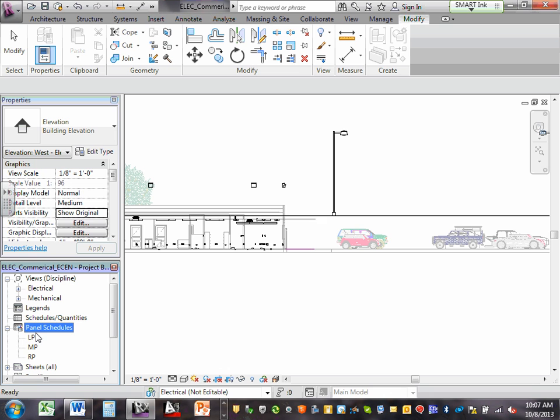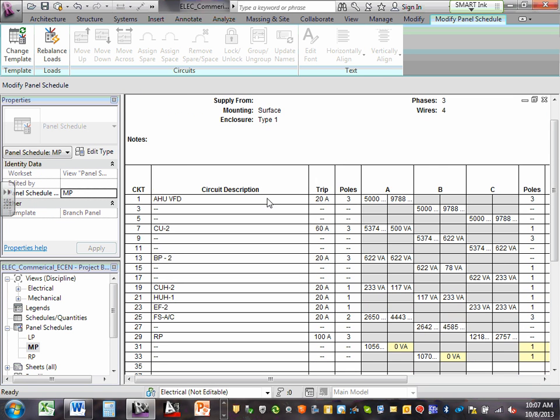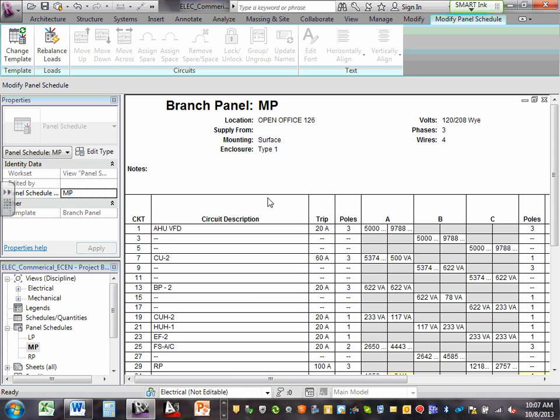If I click on MP, here's the schedule immediately for the MP panel. It's not just drafting — that's why they call it families. When you put a panel, you physically go grab a panel made in 3D with electrical specifications: what's the amps, the voltage, how many slots for circuit breakers — all built into that model. When you grab it and put it on a wall, it has 3D dimensions to the manufacturer's specification.